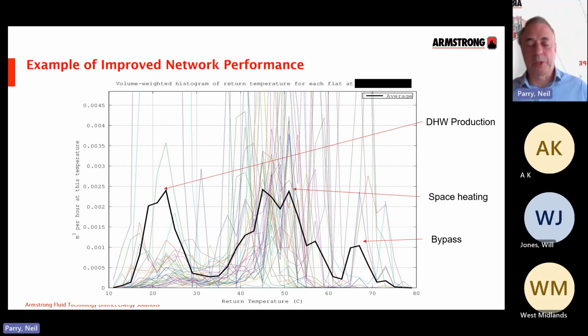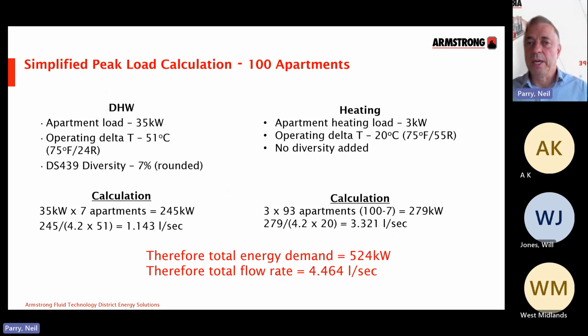Rather than pick an arbitrary flow and return, like saying, well, I'm going to have 70 and 40, hopefully you can see on that graph that if you do that, all you're really doing is putting a sort of stick in the sand where you think the average return temperature is going to be. Much better to do it more accurately and do it in this way. I have simplified this calculation just to show you the general idea of how it's done.